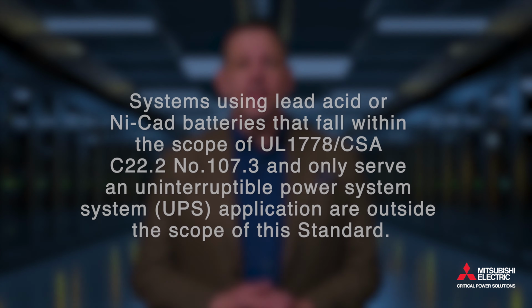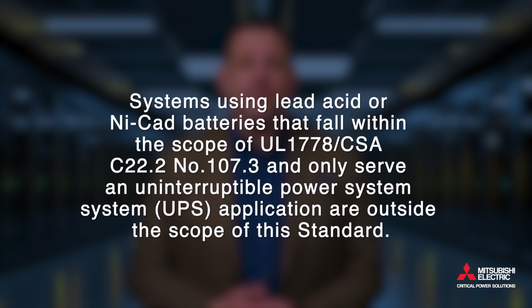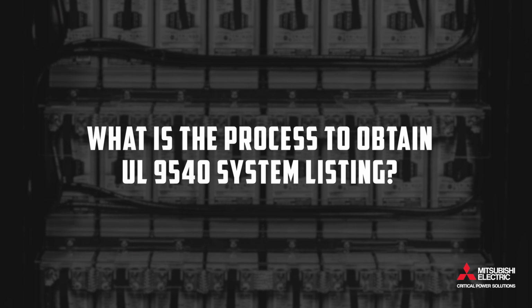In NFPA 855, there were some new requirements, but those are implemented at the discretion of the AHJ. Per UL 9540 3rd edition 1.5, systems using lead acid or NiCad batteries that only serve a UPS system application are outside the scope of this standard. What this means is if VRLA batteries are used with a UL 1778 UPS system in application, they are exempt from the UL 9540 standard.